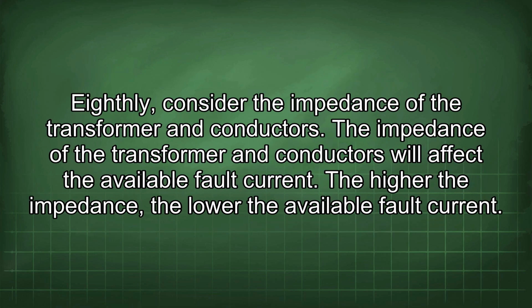Eighthly, consider the impedance of the transformer and conductors. The impedance of the transformer and conductors will affect the available fault current. The higher the impedance, the lower the available fault current.